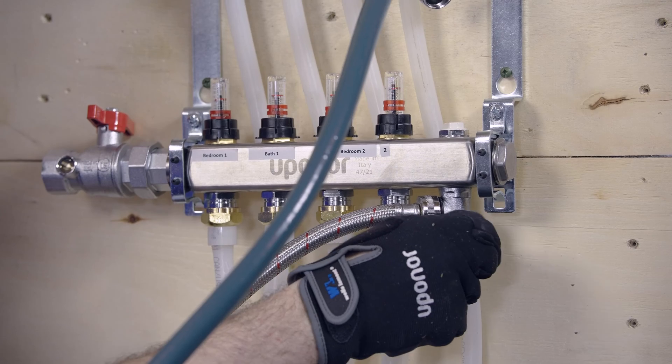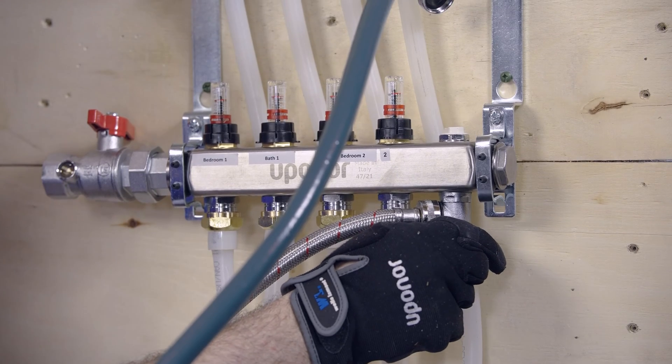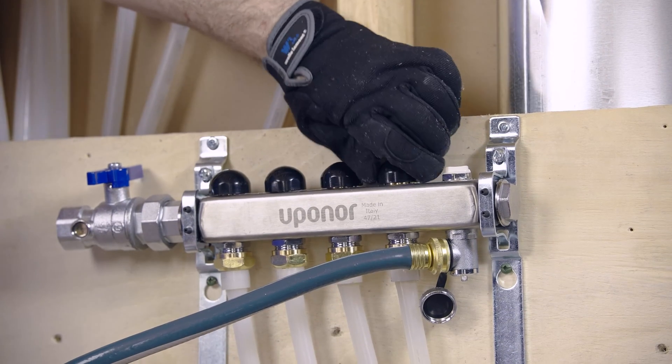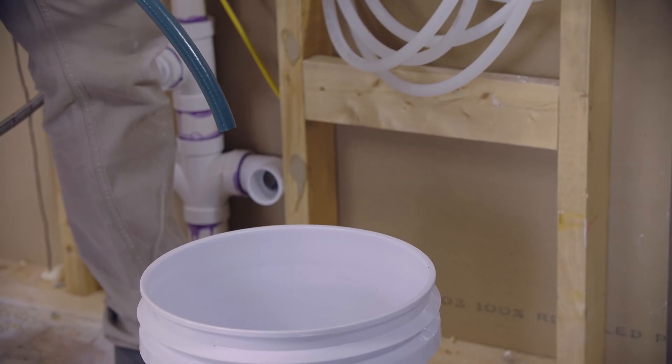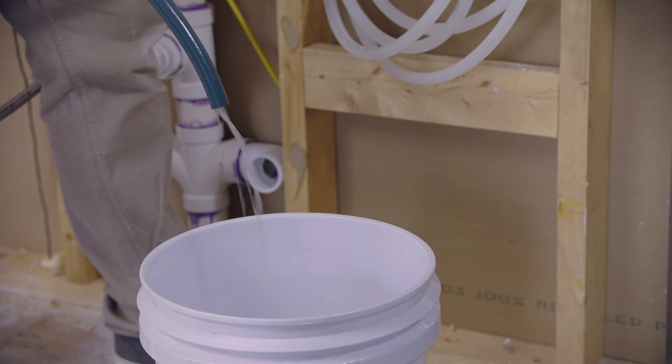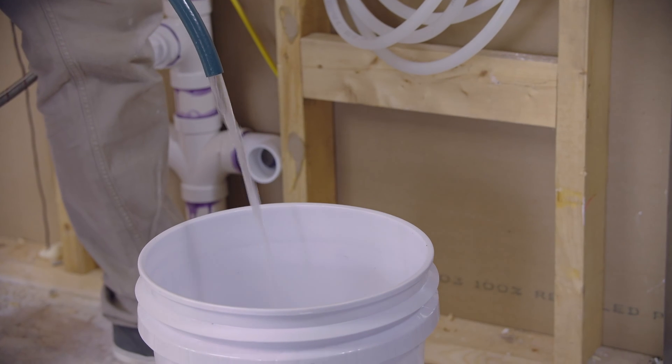Next, turn on the water to the hose and open a single loop. This will fill both the manifold chamber with water and start filling the loop. Water will eventually begin to flow through the drain hose. Allow the water to flow until all the air is purged from the loop.